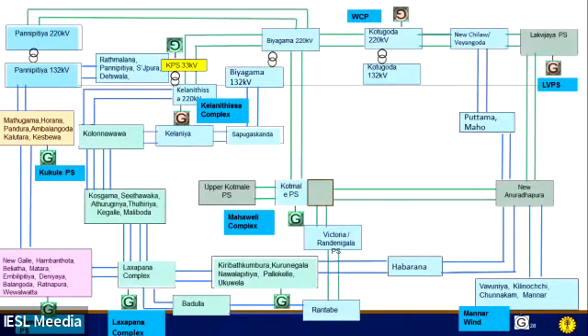The system restoration usually takes place in parallel in different sections of the transmission network. You can see some substations highlighted in light blue, which are restored from the Mahaweli complex as one section of the network. Then substations highlighted in light green are energized from the Laxapana complex in parallel, and substations in the southern network, highlighted in pink, are energized from the Samanala generators. The substations mentioned in light brown are energized from Kukule, and similarly from the Kelanitissa small gas turbines, and a small part of the Kolonnawa supply is restored in parallel. All these are energized in parallel to save time.